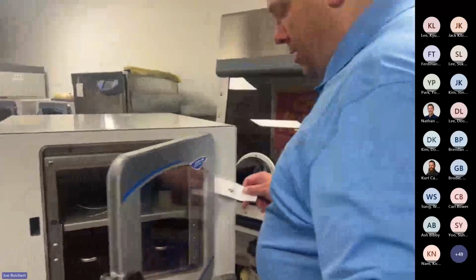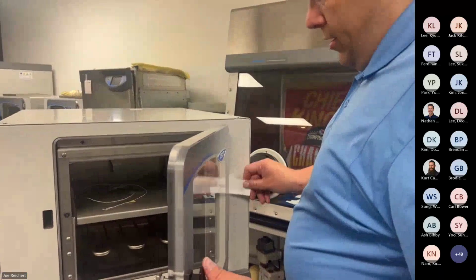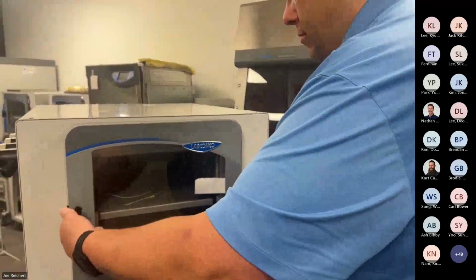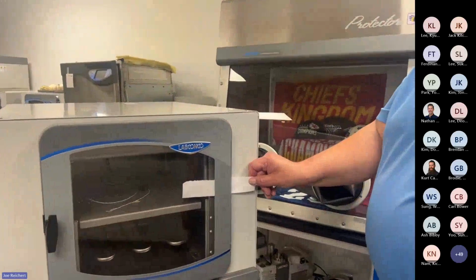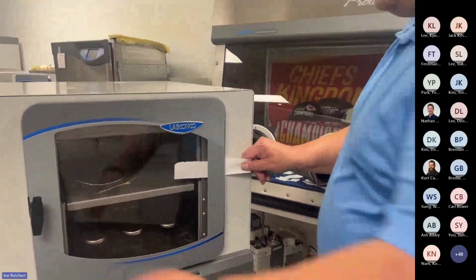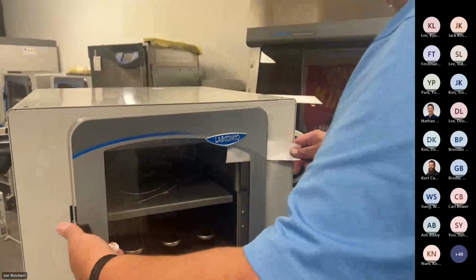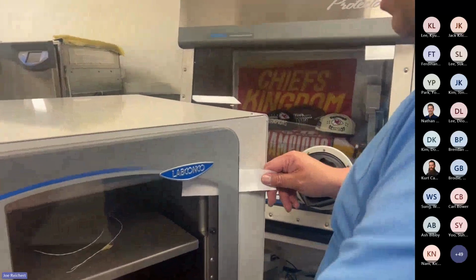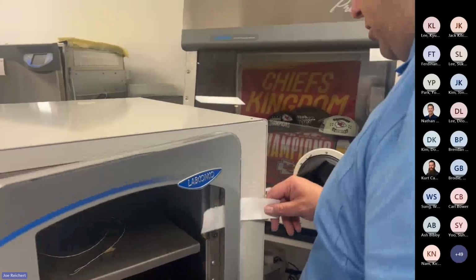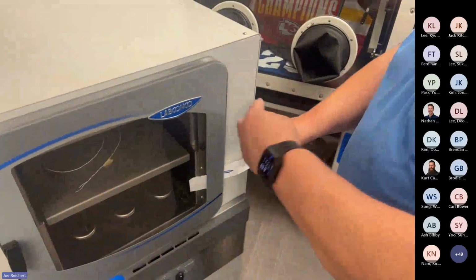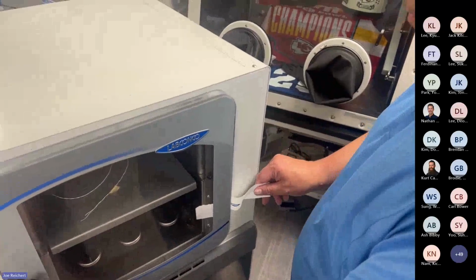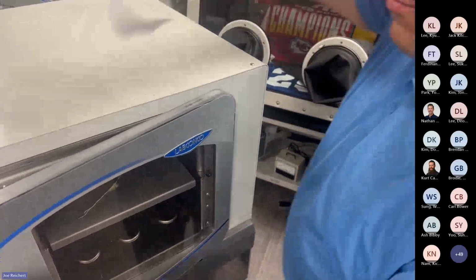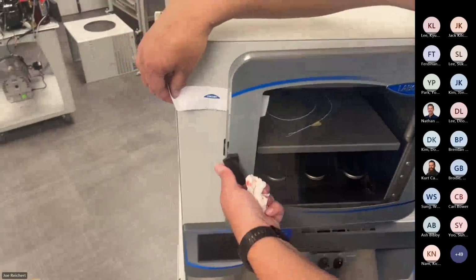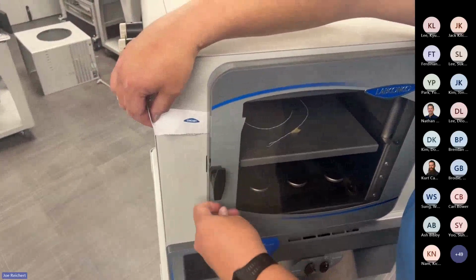And the way you do that test is you can slide it behind the door, close the door, and it should be so tight that it's not going to come out of there. But you can do this test all around it. Hinges are kind of more your susceptible area, easier spots to have leaks because these are adjustable back and forth. You can also do it around the latch. Test it the same way.